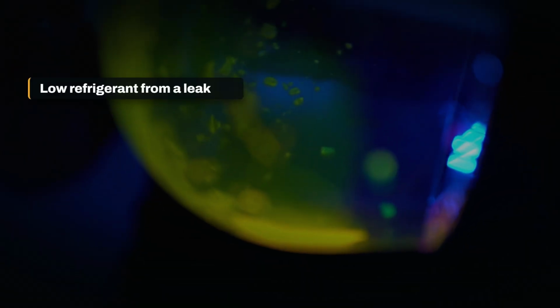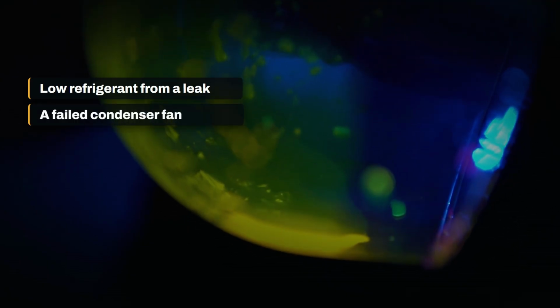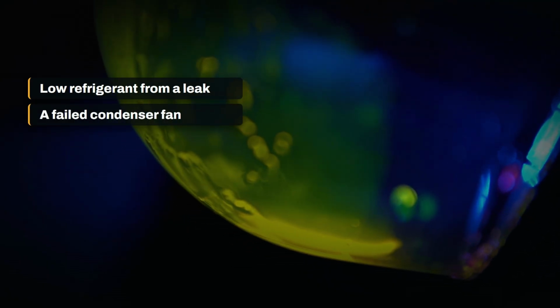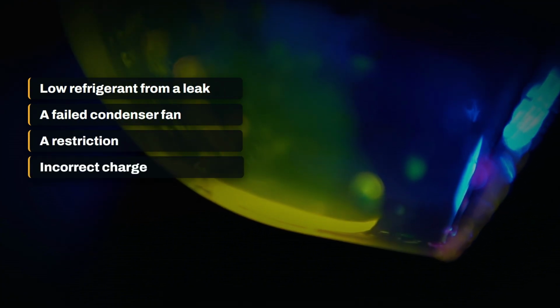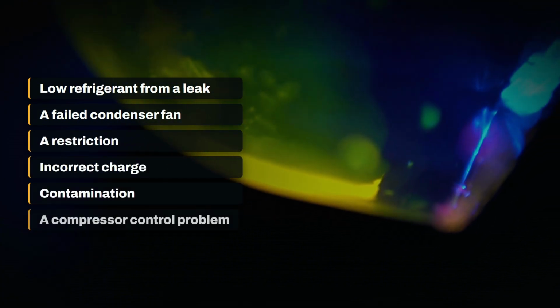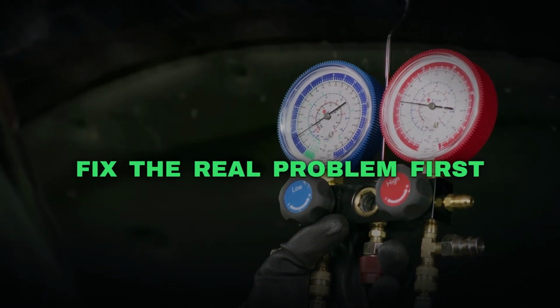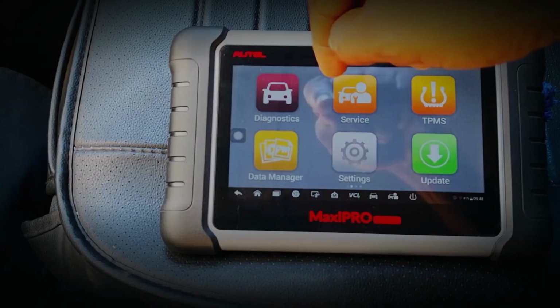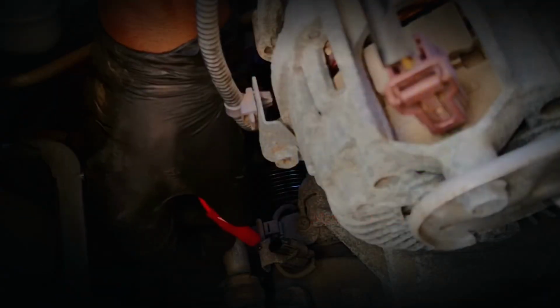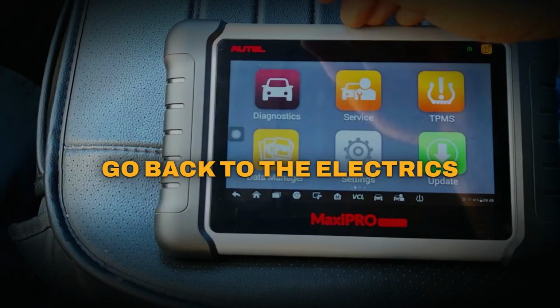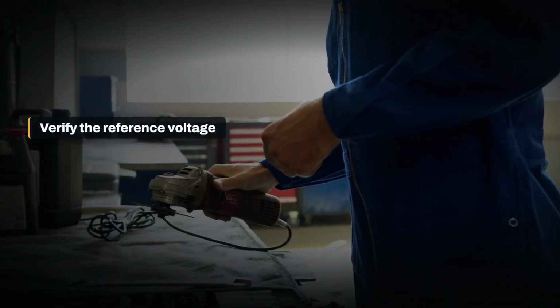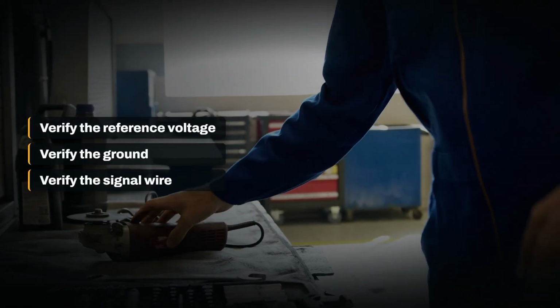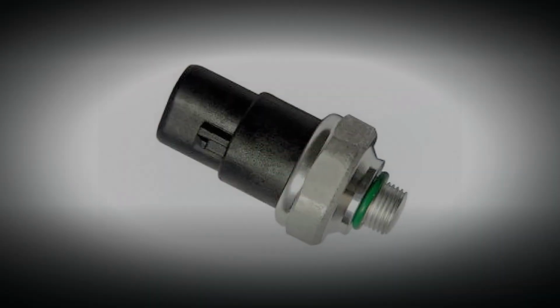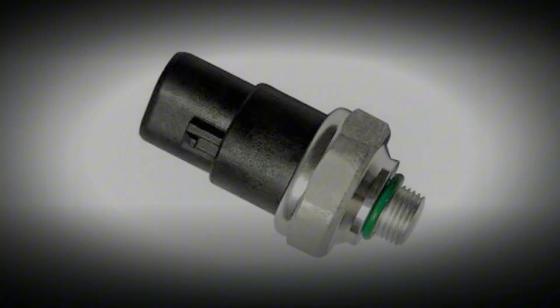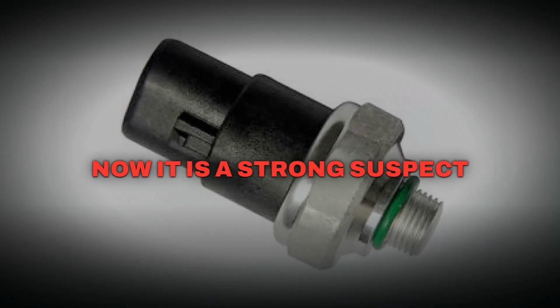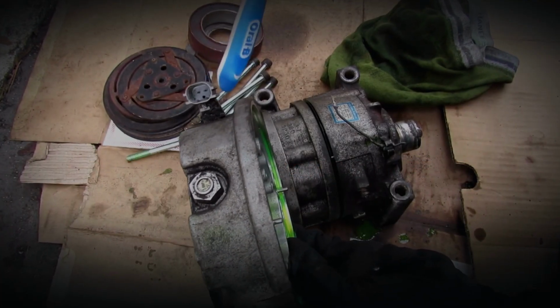The real problem may be low refrigerant caused by a leak. It may be high pressure caused by a failed condenser fan or blocked condenser. It may be a restriction, incorrect charge, contamination, or a compressor control problem. Fix the real pressure problem before replacing the sensor. If the actual pressure is normal, but the scanner reports a clearly different or impossible value, return to the electrical checks. Verify the reference voltage, verify the ground, verify the signal wire. If those circuits test correctly, and the scan reading still does not match actual pressure, the pressure sensor becomes a strong suspect. This comparison should be done with the correct refrigerant equipment.